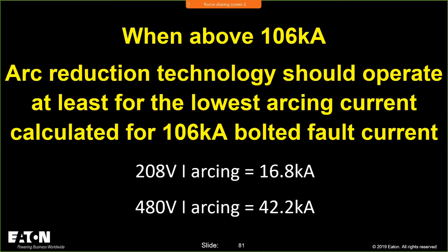Now, when I'm above 106,000 amps, what I did here is I calculated the arcing current at 106,000 amps at both 208 volts and 480. If you employ an arc reduction technology, you'll have to make sure that it can actuate based upon the arcing current at the largest bolted fault current that we can calculate, which is 106,000 amps, for a 208 volt and a 480 volt system. Those are the numbers. I didn't do a 600 volt system. I can do that, but I'll do that later. But if you're on a 480 volt system, make sure your technology actuates at 42.2 or greater. And if you're at 208, make sure you are actuating at 16.8 or greater.